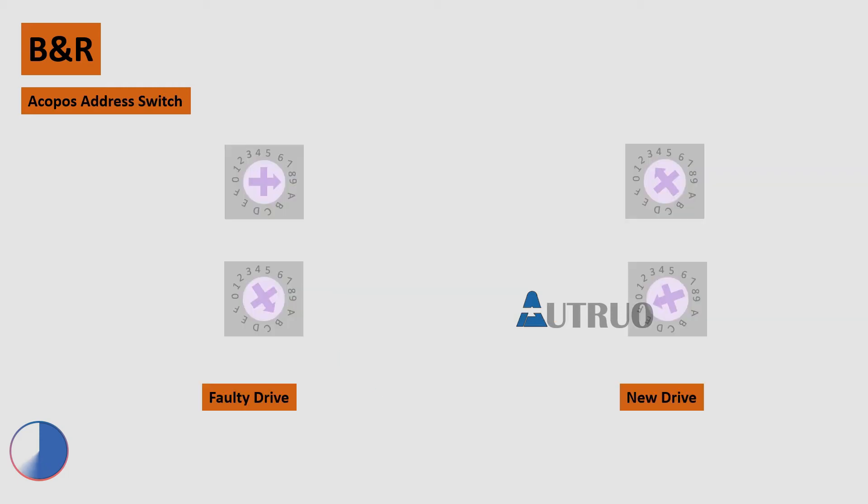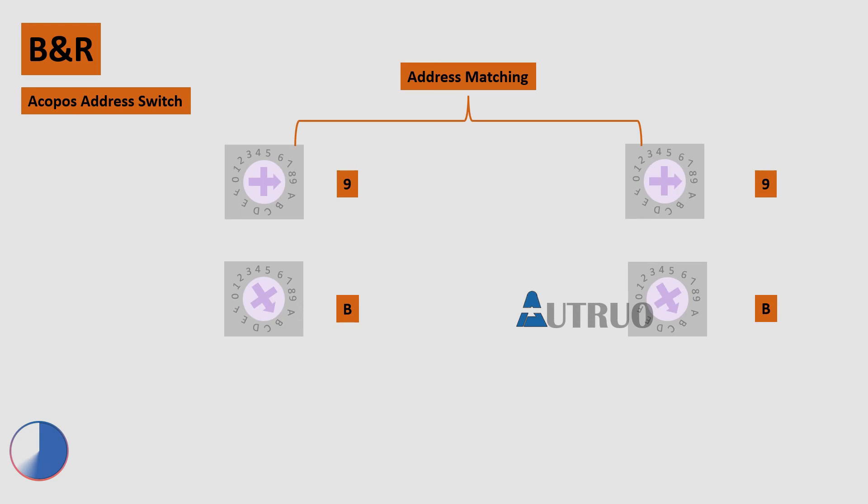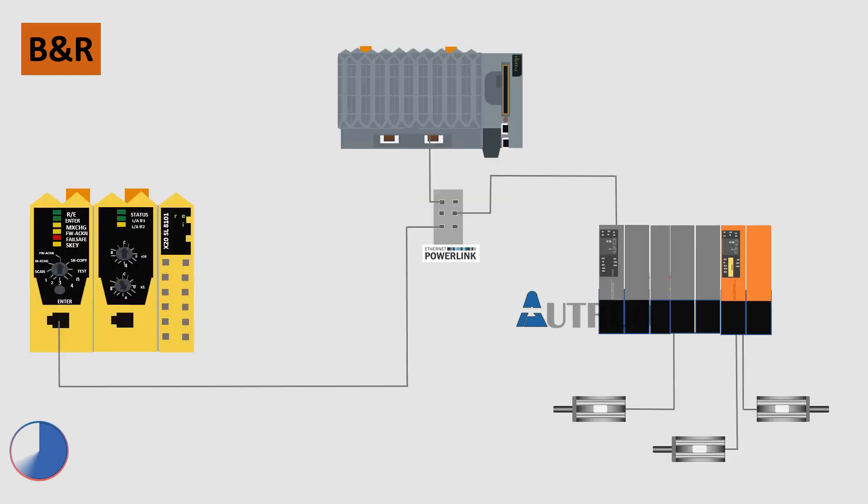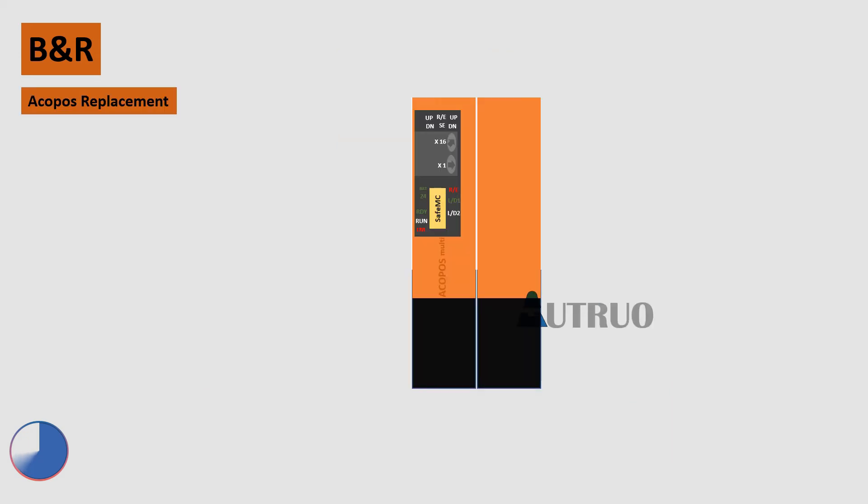Set the address of the new drive to the address of the old drive. After setting up, install the new drive to the bus bar and power up. After powering up, sometimes the new drive will not be recognized by the system. For confirmation, the new ACOPOS LEDs will be blinking red and the run LED will not be lit.